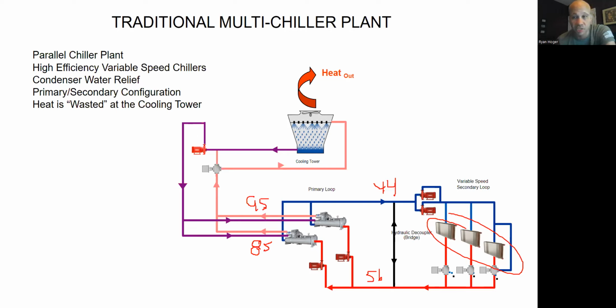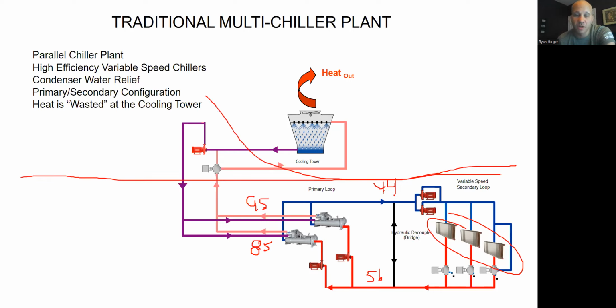So once again, I'm cheating by moving heat from a cool area to a hot area. I'm cheating physics by using the refrigeration cycle and boosting the pressure. That allows me to take that heat and shove it into this relatively warm 85-degree water, and hence the water warms up to 95. Then we send that water outside. So here's the roof of the building. Actually, these circuits are probably inside the building. We send this water outside.